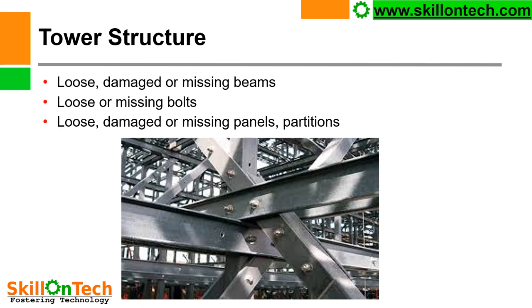Loose or missing bolts — bolts can fall into the cooling water basin. Loose, damaged, or missing panel partitions — cooling tower cells have partitions which can also be damaged during operation due to vibrations. All these tower structures must be inspected carefully, all observations recorded and rectified whenever a shutdown is taken for cooling tower maintenance.